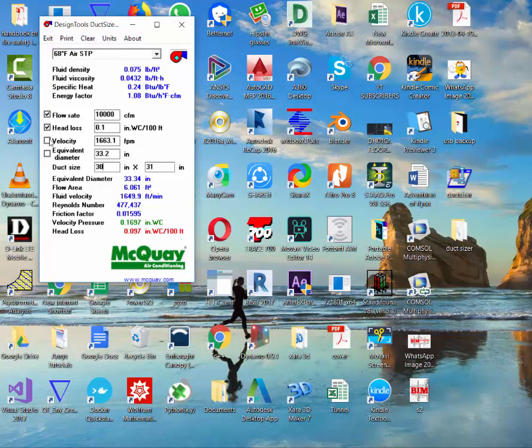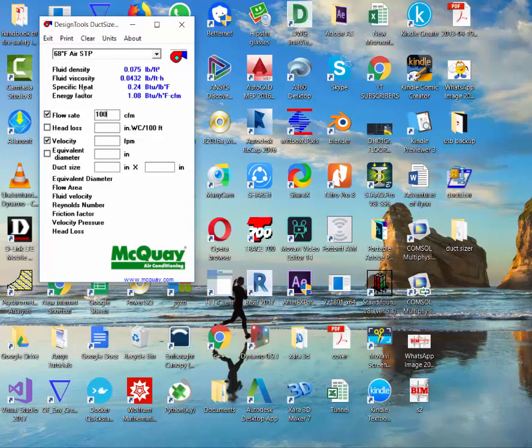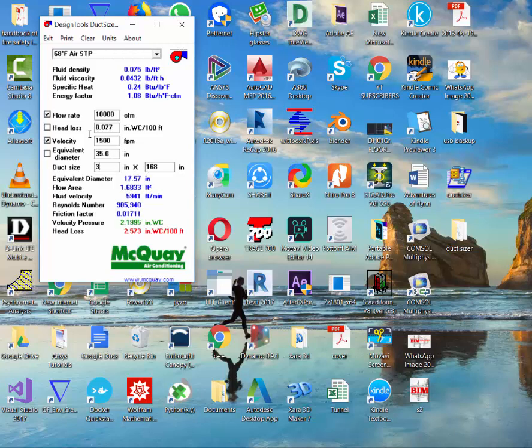Sometimes you would not like to use the head loss; you may like to use the velocity. So this is around 10,000 CFM. If you have the same velocity of around 1,500 FPM, you can use a simple method and size it at 30 by 32, or 32 by 32 is the size of the duct.